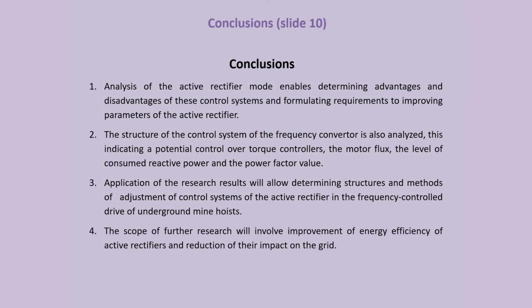Conclusions. Analysis of the active rectifier mode enables determining advantages and disadvantages of these control systems and formulating requirements to improving parameters of the active rectifier. The structure of the control system of the frequency converter is also analyzed, this indicating a potential control over torque controllers, the motor flux, the level of consumed reactive power, and the power factor value. Application of the research results will allow determining structures and methods of adjustment of control systems of the active rectifier in the frequency control drive of underground mine hoists.